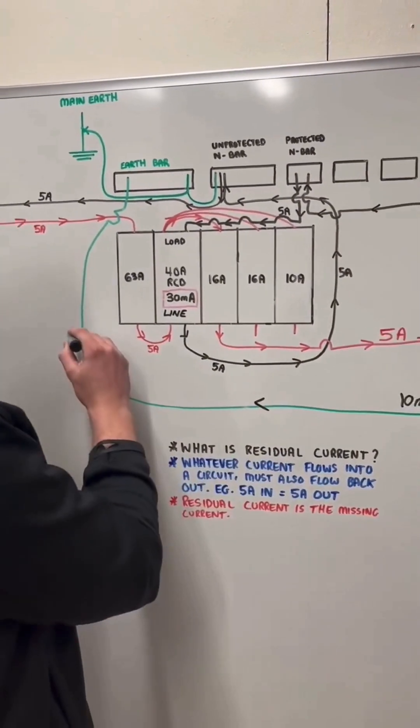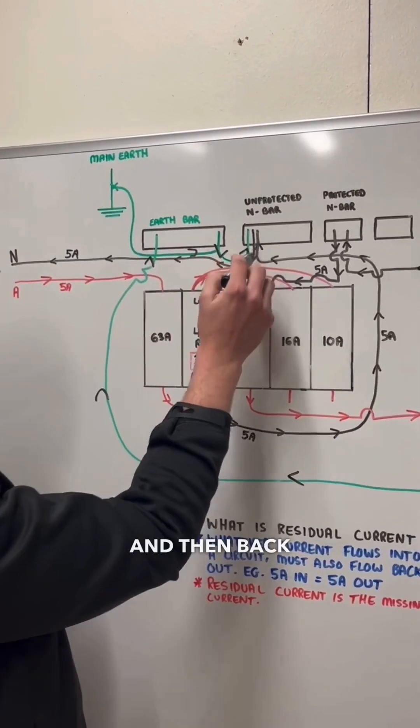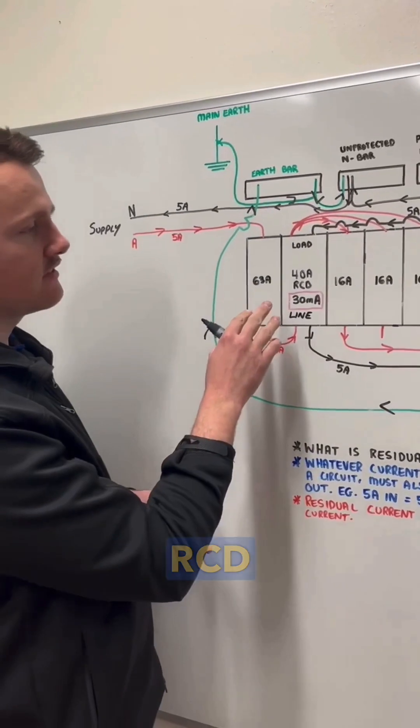That current will just travel up through the earth bar, across into the MEN and then back through the neutral that way. So it's still going to get back to its source and the RCD won't trip it off.